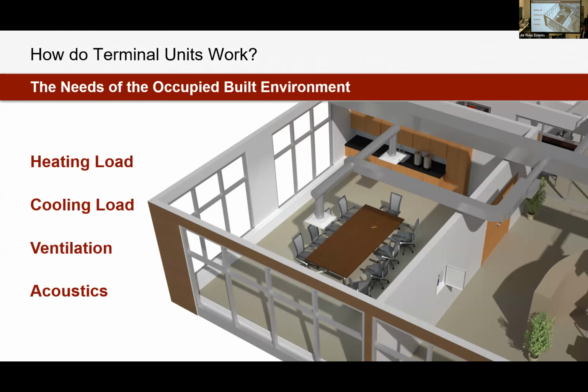So in our modern day buildings, terminal units are used to create zones within our space. Inside of those zones, we can use a terminal unit to regulate the airflow. That could be our cooling load. Usually we're supplying fresh conditioned air from the air handler through our terminal unit. We're going to regulate that volume of air with the terminal units, so we're modulating our cooling load as well as the ventilation air in the space.